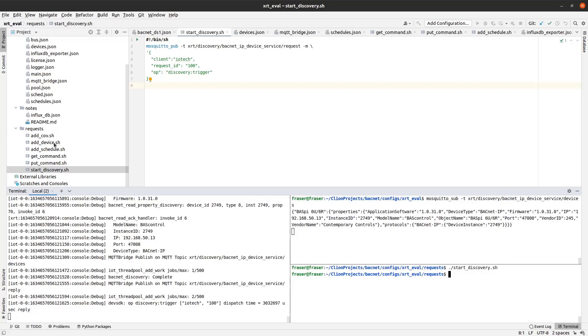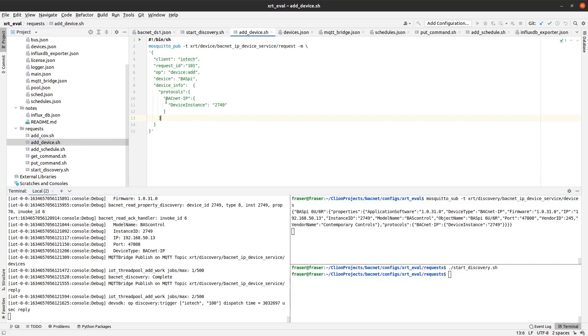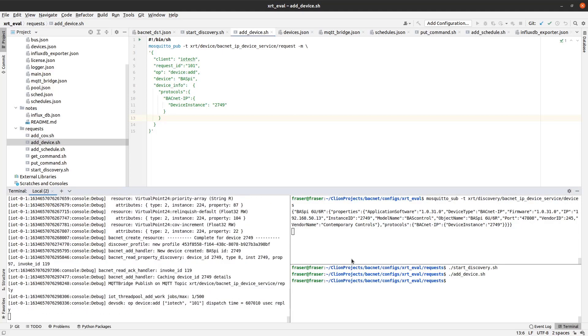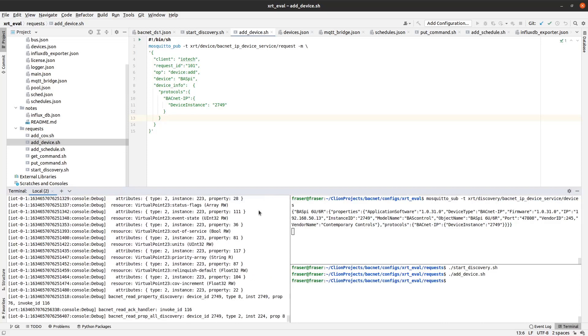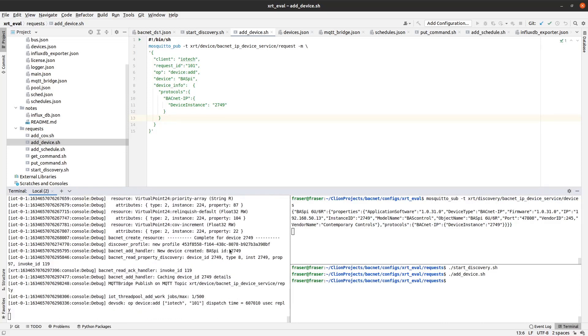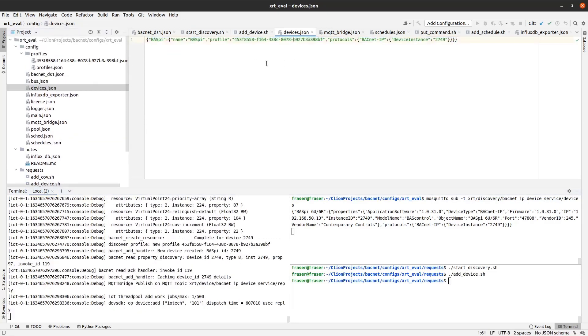The next thing that we're going to do is to use the discovery information to add the BACnet device to XRT. You can see the payload for the JSON message which includes the device instance identifier that we will send to XRT via MQTT to add the device. If we then run the add command from the second console, XRT will provision the device that has been discovered. A new entry will be added to the devices.json file as shown. Device configuration files, which we refer to as device profiles, will also be automatically generated.